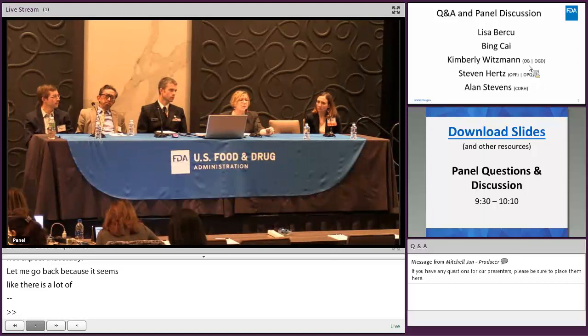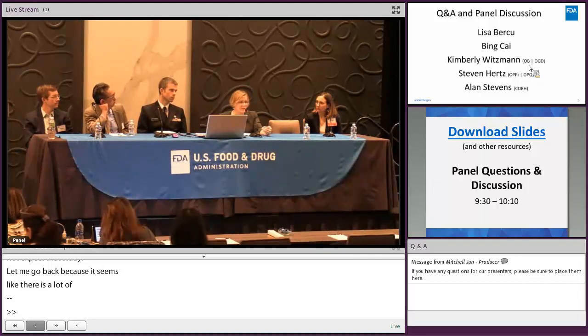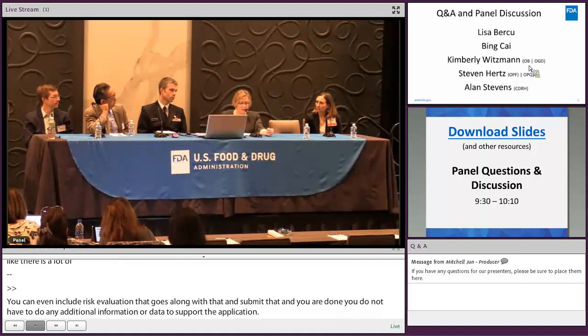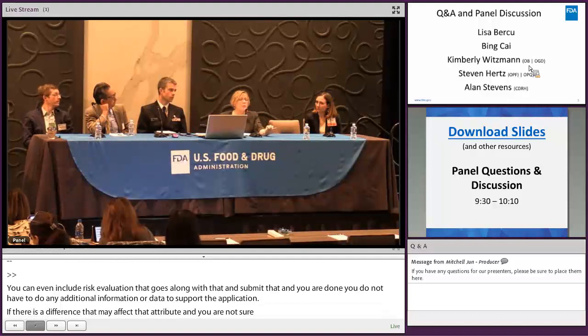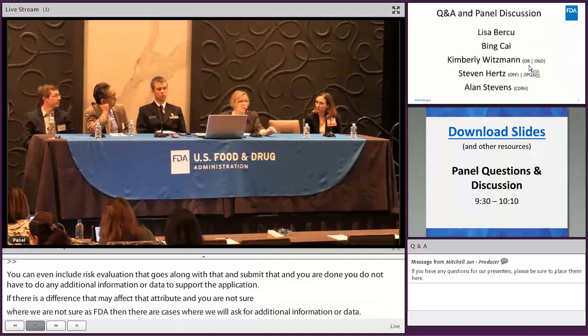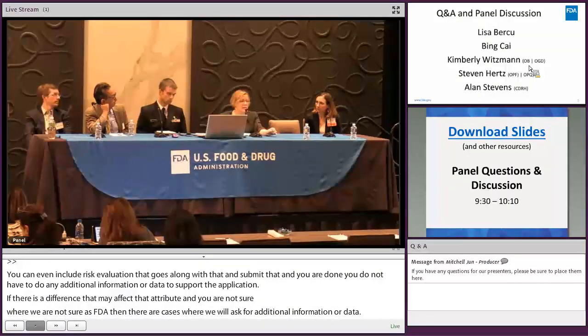If there's a difference that may affect an external critical design attribute, and you are not sure, or we are not sure as FDA, then there are cases where we will ask for additional information or data. One type of additional information or data is what we've termed a comparative use human factor study. Okay? There are many other kinds of information we could ask, many other kinds of data.